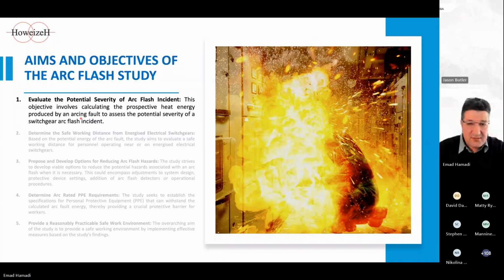First, the study aims to evaluate the potential severity of an arc flash incident in different parts of the network. This could involve calculating the prospective heat energy released by an arcing fault in various locations. By doing that, we can identify the weak points of the electrical network and understand the severity of the risk in different sections, which could be crucial for the company's HSE department, for example, as it allows them to conduct a more accurate risk assessment and implement targeted measures to enhance safety and reduce the risk, or choose the right PPE and so on.